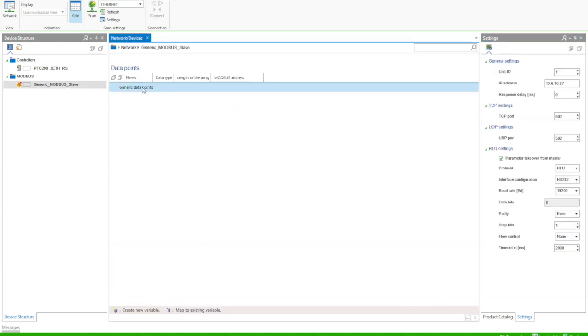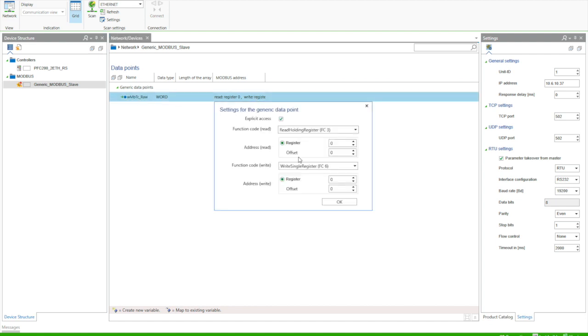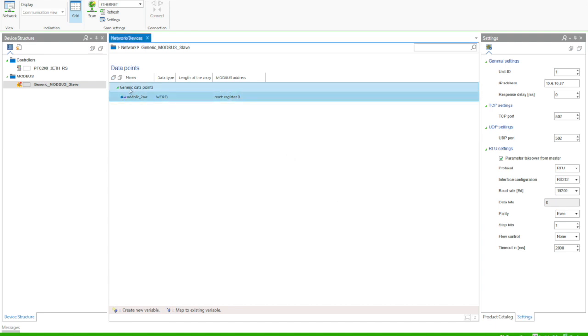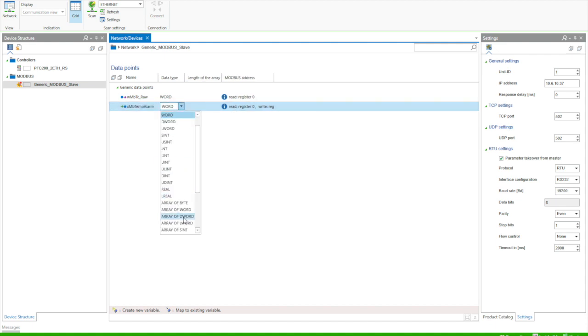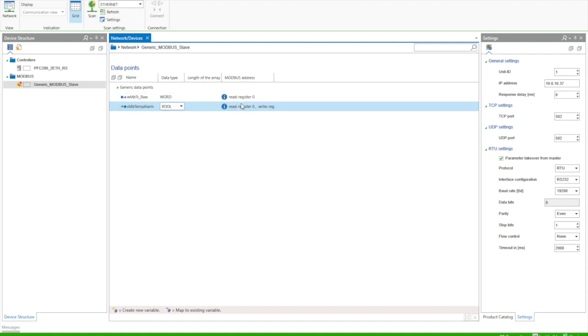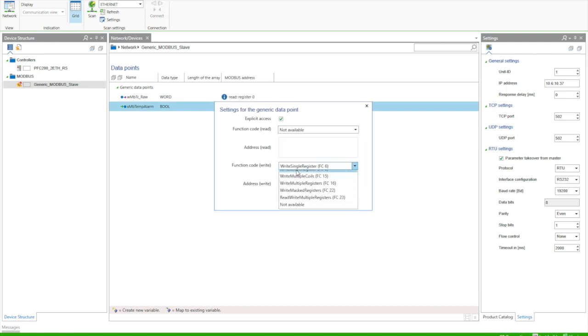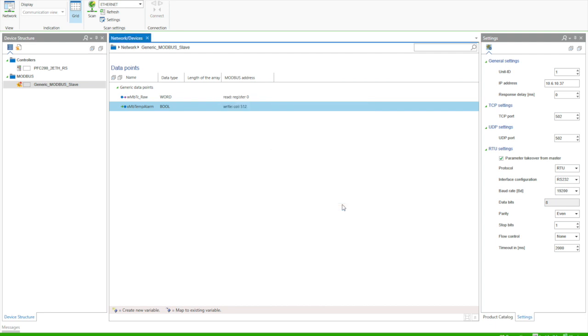Now if I double-click the Modbus slave, I can just right-click on generic data points, and I can add a variable as I like. The difference here is I can select whether it's read or write, and I can select the registers in which I want to map this. So I'm just going to map the thermocouple input word zero, and I'm also going to set my alarm as a boolean. I'm only going to write a single coil, and I'm going to do this from address 512, which is the address spelled out in the manual.